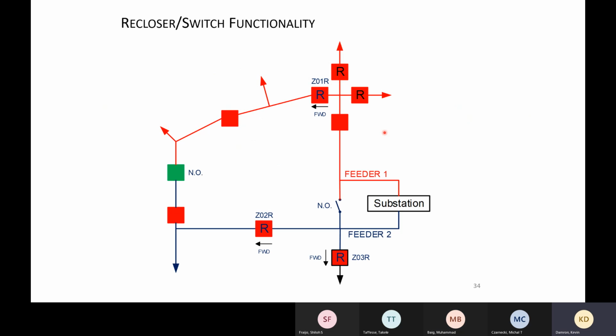So, another example. This is a little more complex system. Here we've got a substation with two feeders coming out of it, and this feeder goes up. In this case, we've got three reclosers in three different sections. Normal power flow is Z01 and down to this normally open point. On feeder 2, I come out and I've got Z03 forward and Z02 coming over here, again to this open point.